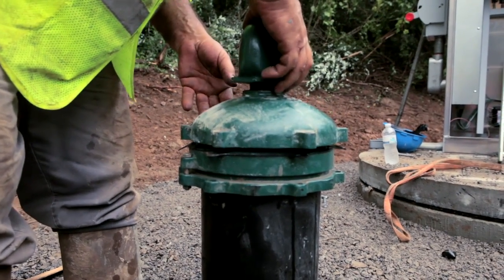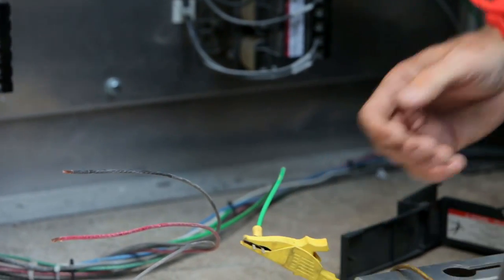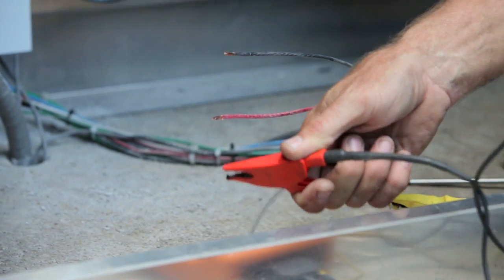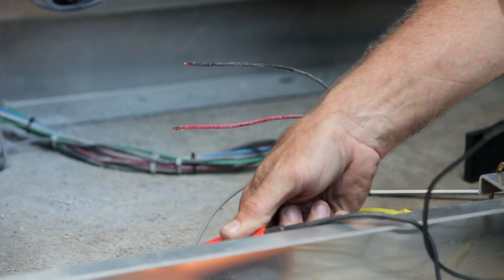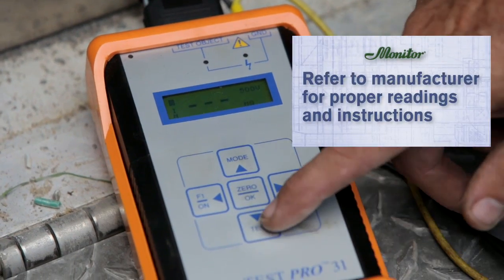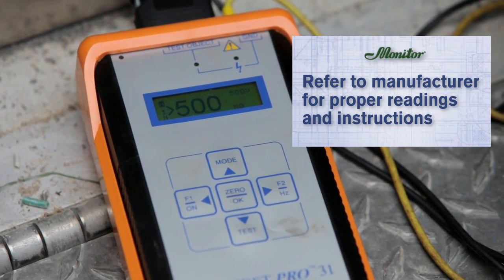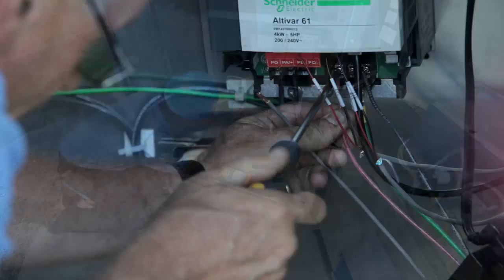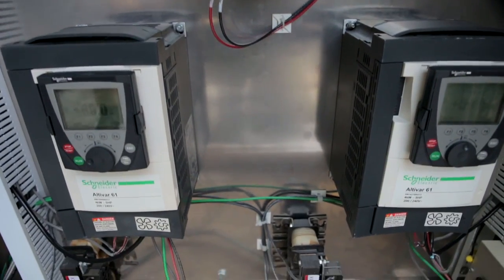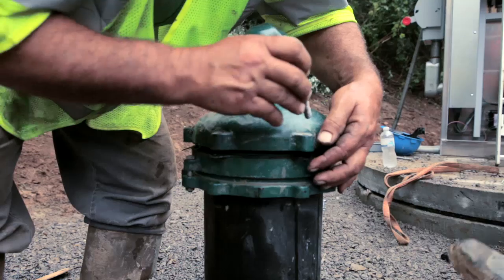To confirm continuity of all splices, complete a megohmmeter test on the submersible motor leads at the control panel. The submersible motor needs to be fully submerged in water — in particular the splice — to properly confirm the splices were done correctly. Refer to the motor manufacturer for proper readings and further instructions. If the megameter test is acceptable, connect the leads to the output of the VFD located inside the control panel. You may now finish the installation of the monitor pitless booster station by securing the cap to the upper casing.